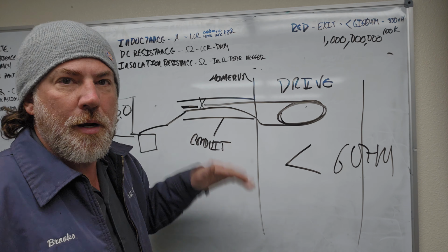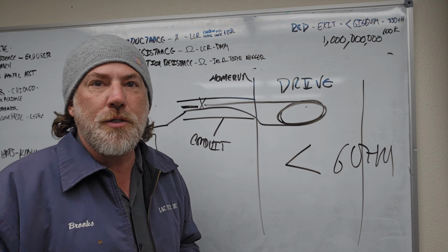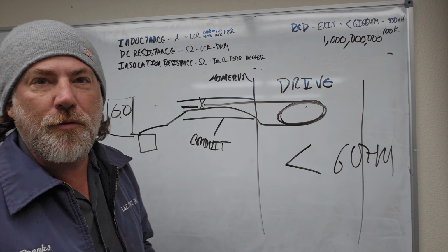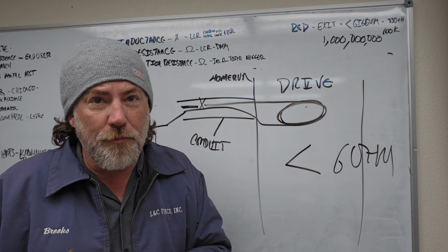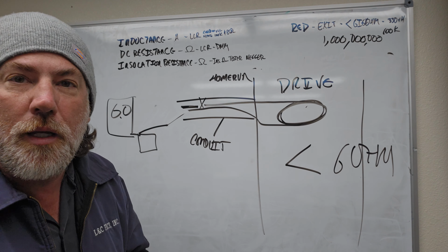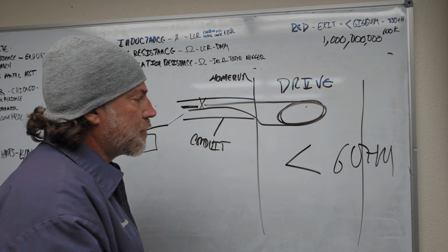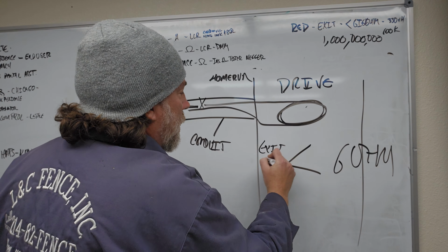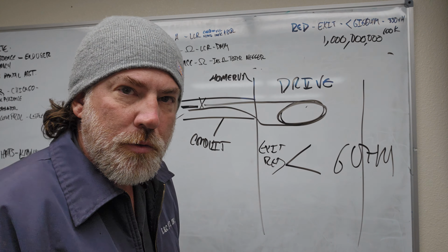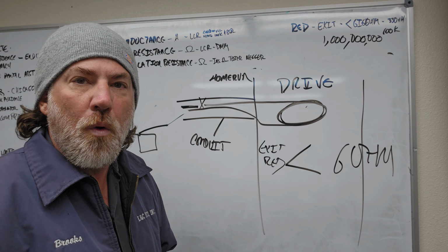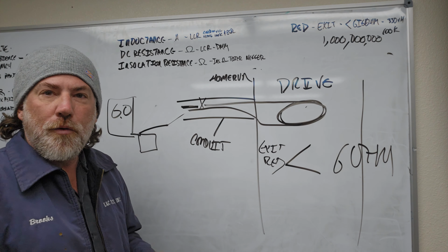Do you see this kind of breaking down in your head now, Ruben? Where you're flawed in your logic, where these two other devices will lead you in the direction of the quality of the loop. You have your meter on one lead, your Megger on one lead, you get above a gigohm. So in this case, exit, red, above 1 gigohm. You have one of only 3 faults, which I'm assuming you don't know, only three faults that a conductor can have. You have one of 3 faults.